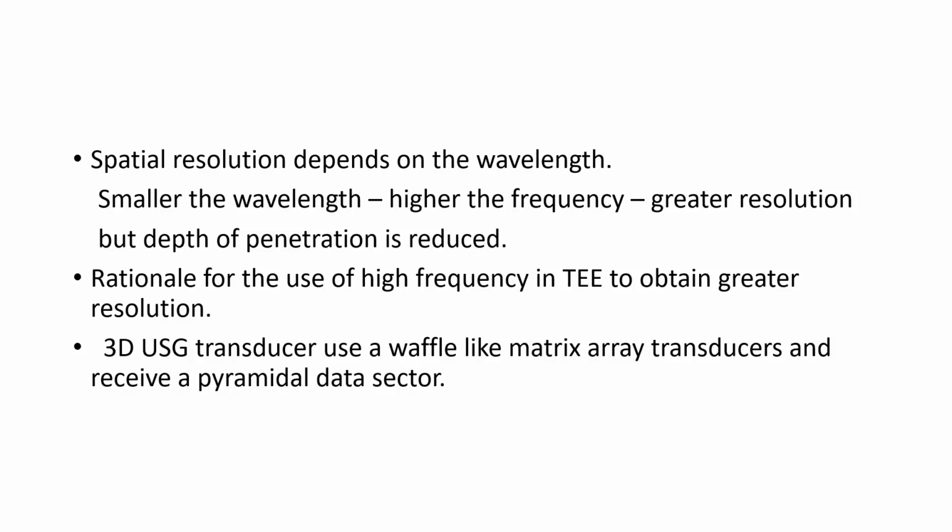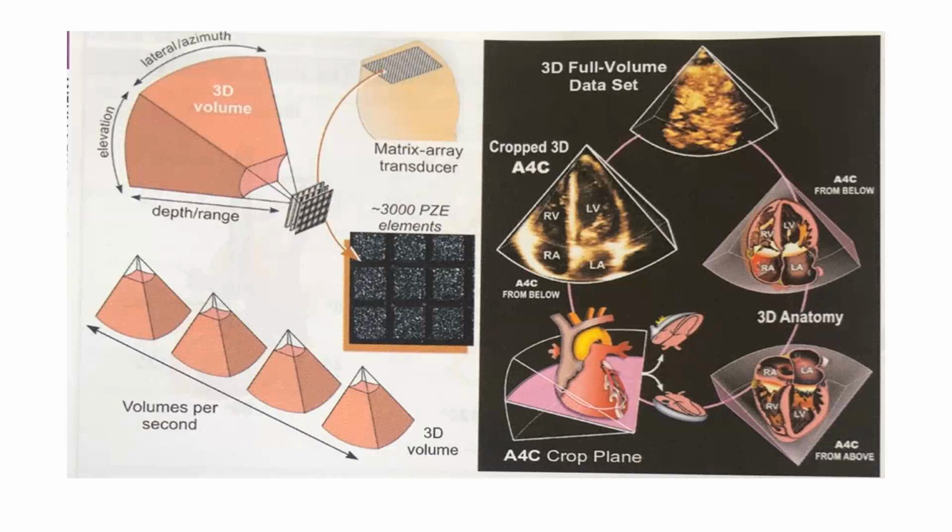Nowadays, 3D USG transducers are also available, which use a waffle-like matrix array of transducers and receive a pyramidal sector of data. It is depicted here. This is the transducer with a waffle-like array, which receives a pyramidal sector of data, and it is then converted and imaged into a three-dimensional structure.